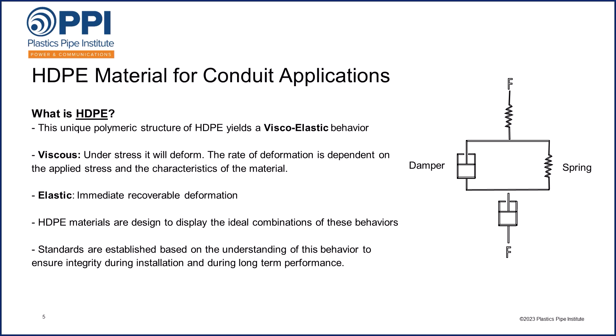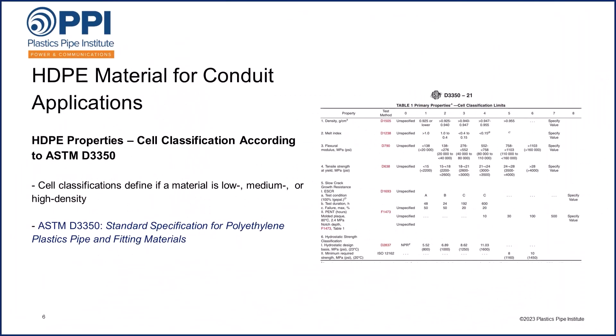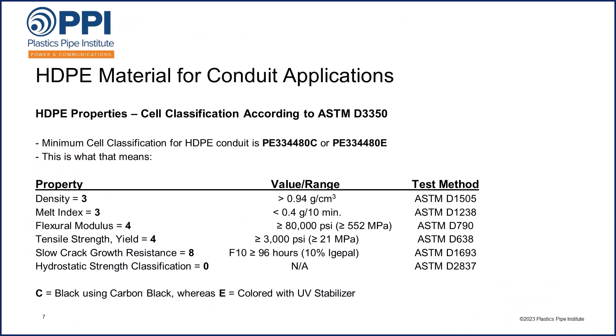For industry standards and specifications, these properties are specified according to a system known as the cell classification. The cell classification system is published in the ASTM standard D3350. This table is an excerpt from ASTM D3350. The cell classification defines whether a PE material is considered low-density, medium-density, or high-density. Today we will only talk about high-density products as used in HDPE conduit. If you have looked at HDPE conduit standards or a conduit manufacturer's specification, you may have seen the minimum cell class specified as PE334480C or PE334480E, and you may wonder what those numbers mean. Those numbers are part of the cell classification as defined in ASTM D3350, as shown below.